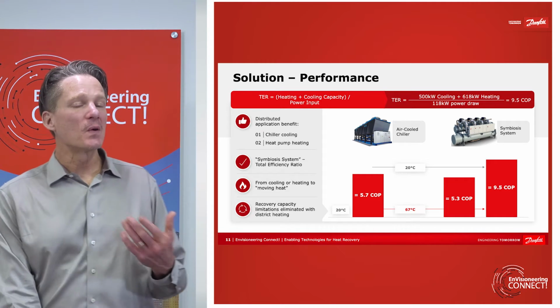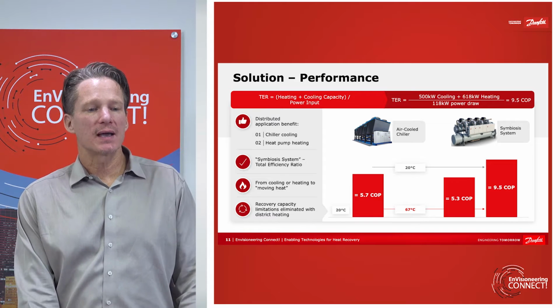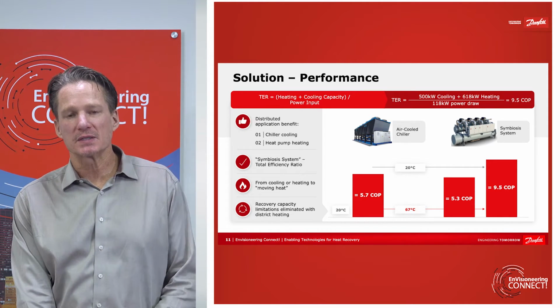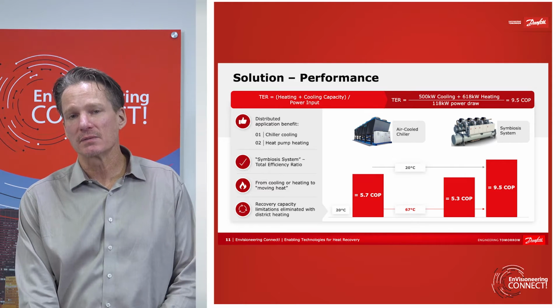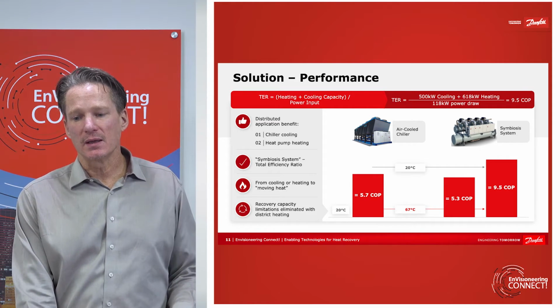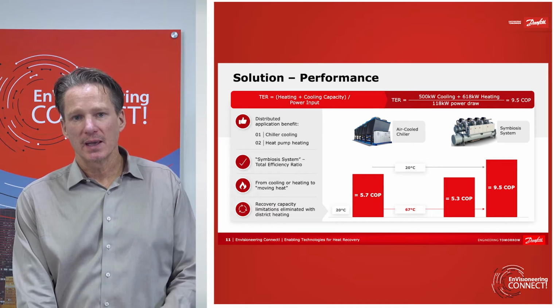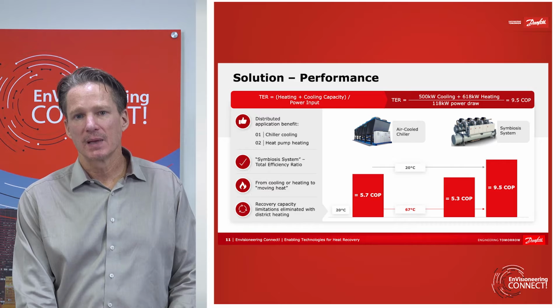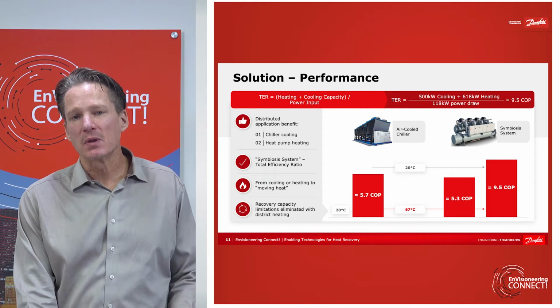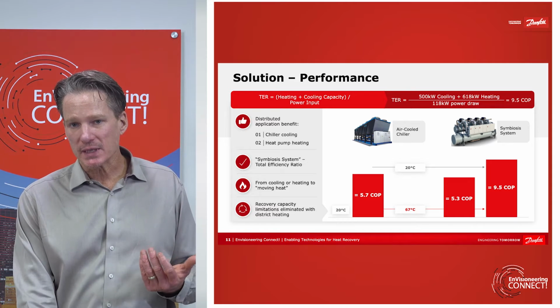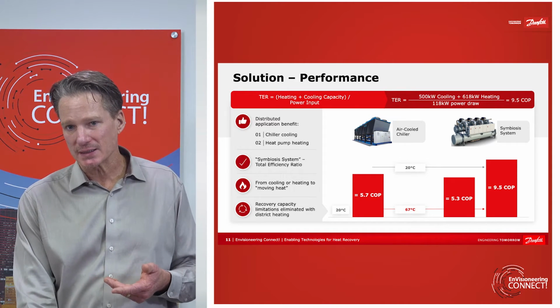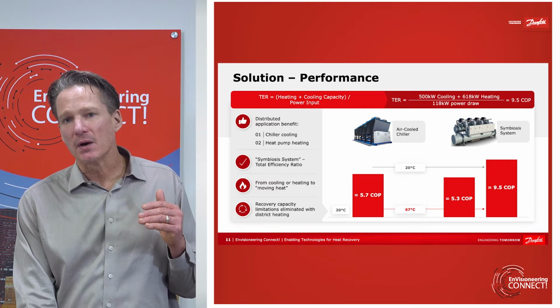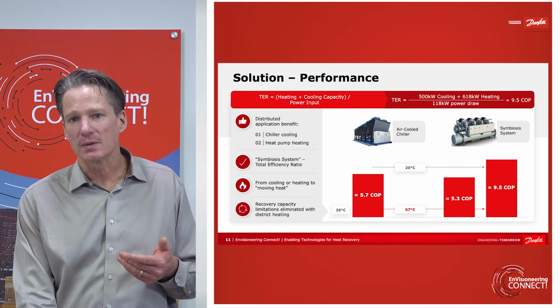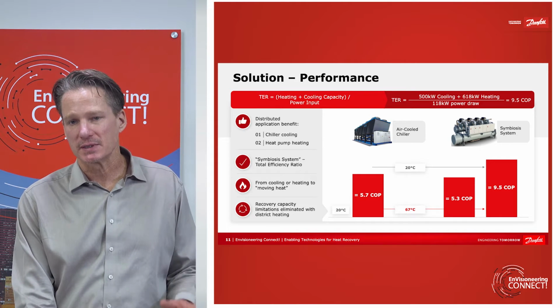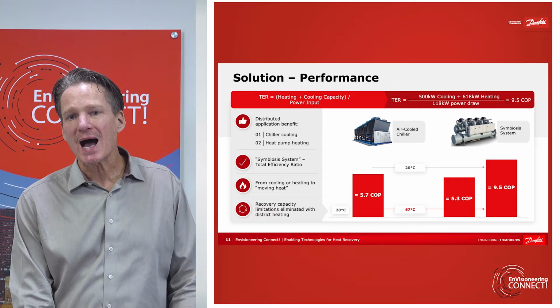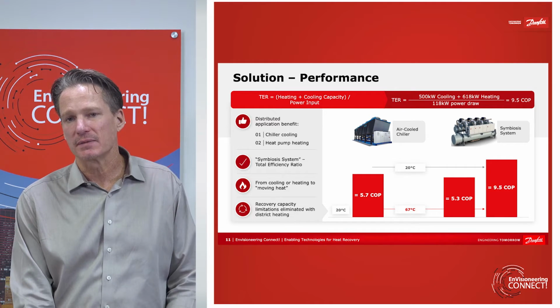So the main point that we're again trying to make is that when you transition to an electrified heating system via water-to-water heat pumps, one of the first realizations you come to is that every chiller is a heat pump and every heat pump's a chiller. It's just whether you're making use of both all the time. And when you take advantage of both the cooling capacity and the heating capacity, and then divide that by the overall power usage to provide both, then the efficiency, or the symbiosis efficiency that I was talking about earlier, is significantly higher than the individual cooling or heating efficiency.